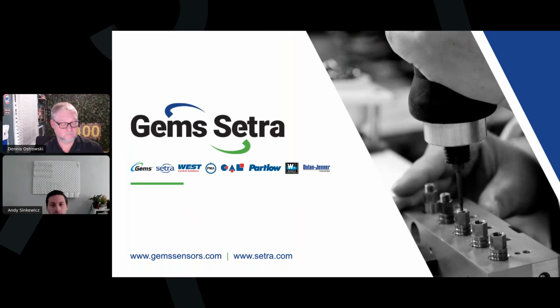All right. So you mentioned BTU measurement. Does it have a second temperature sensor connectable, as the pair of sensors is normally needed for BTU measurement? No, this just has one. I don't know if any customization's ever been done to where it can all be done in one device. But again, the BTU measurement requires, as you said, it requires two. There would have to be a secondary temperature sensor supplied by the user and then it would work in conjunction with the XFT to calculate that in your building automation system or your controller or whatever you're using to operate your application.